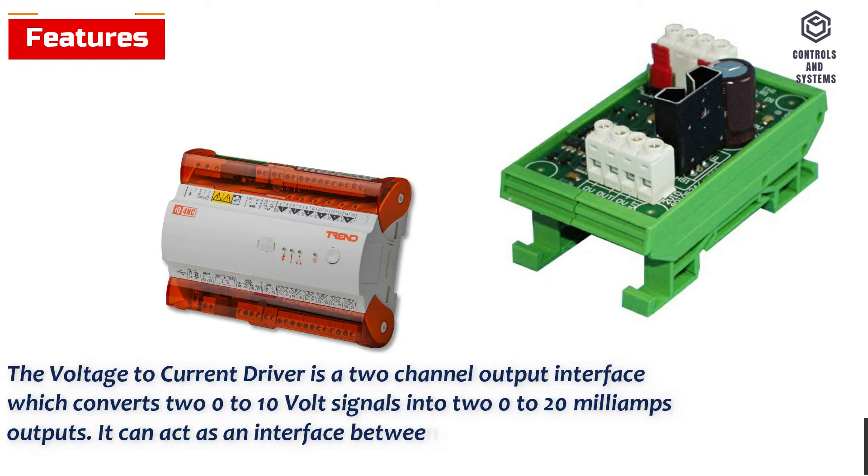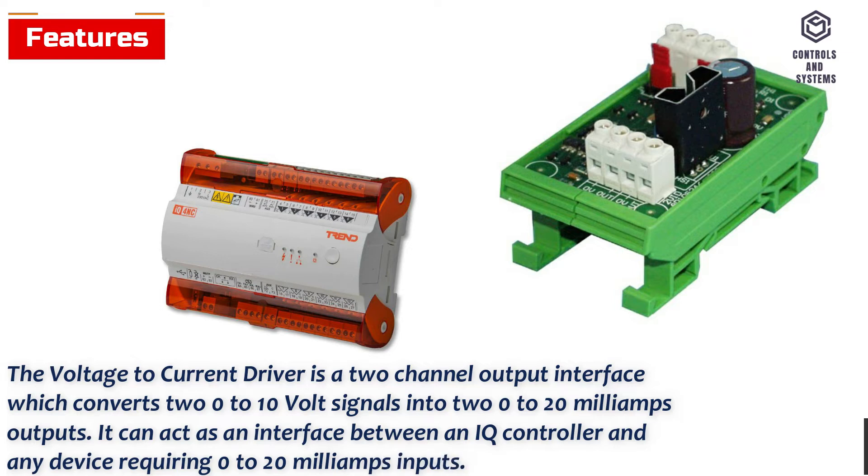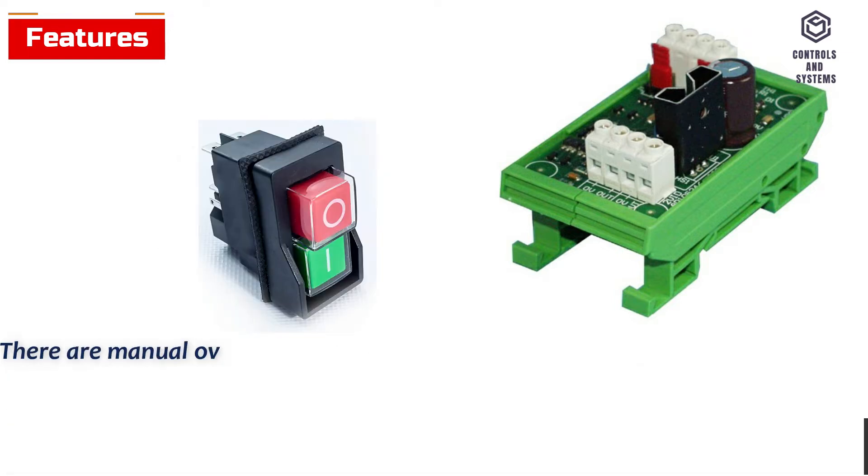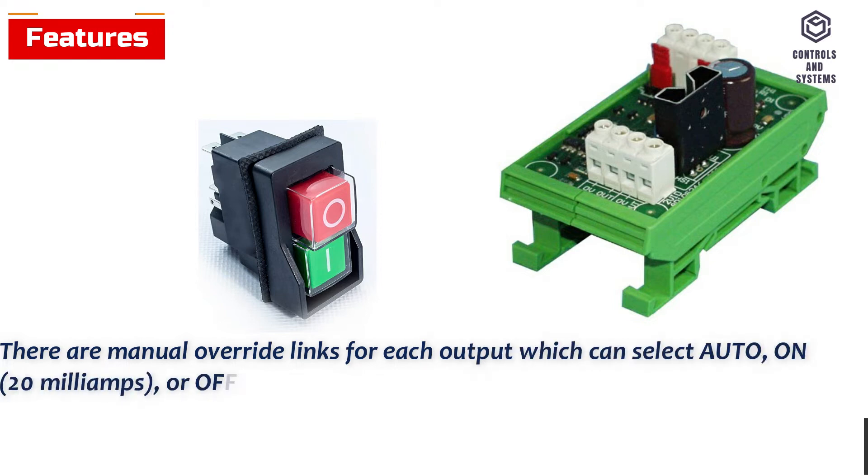It can act as an interface between an IQ controller and any device requiring 0 to 20 milliamp inputs. There are manual override links for each output which can select auto, on 20 milliamps, or off 0 milliamps, and can be used to aid commissioning.